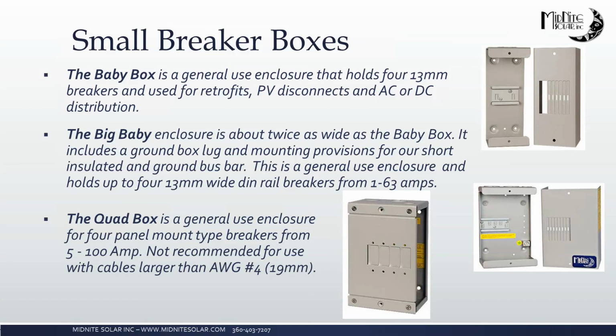And then if you pull up on the top of the box and slide it back in and set the box back down on it, you can put the screws back in it. That gets a little tricky with number 4 wire. And if you're doing a couple classics, and you're going to use these for the breakers for the classics, do yourself a favor and get one per classic, because you will like yourself a whole lot more after you get done trying to install that number 4 wire.